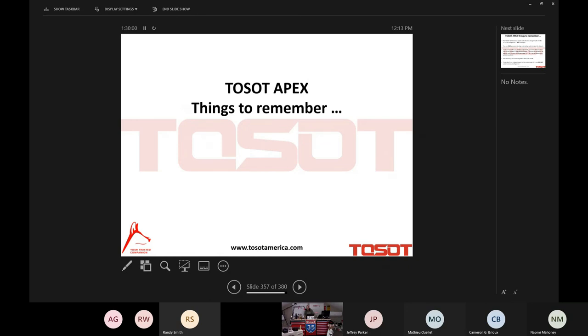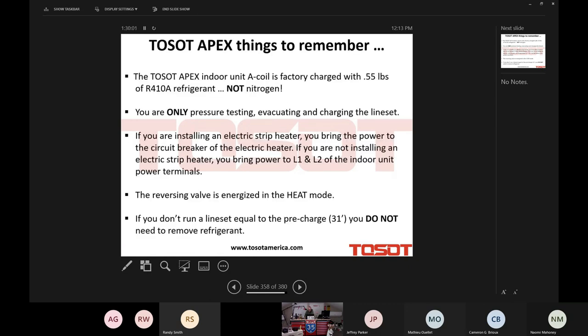So quickly, in recap, some things to remember. Tosot Apex indoor unit A-coil is factory charged with R410A, not nitrogen. Don't release it. You are only pressure testing, evacuating, and charging the line set. If you're installing the electric strip heater, you bring the power to the breaker supplied with the heater. You only go to L1 and L2 of the indoor unit if the electric kit is not being used.